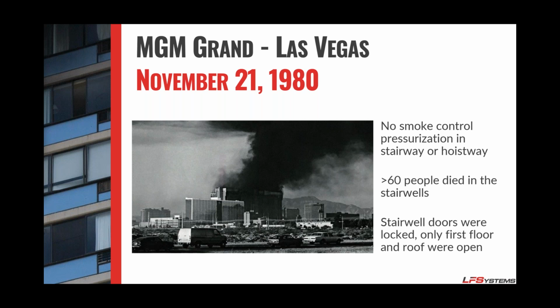Unfortunately, there was no smoke control system in the building, so nothing in the stairwell, nothing in the elevators. In addition, the AC unit was not tied into the fire alarm system, so it didn't shut down return air ducts. It didn't do anything to prevent smoke from traveling from one point to the other. Part of that was a passive stairwell system, which we can talk about in another presentation. There were 85 people that perished in this event. Over 60 of them were in the stairwells, and it was due to smoke inhalation.